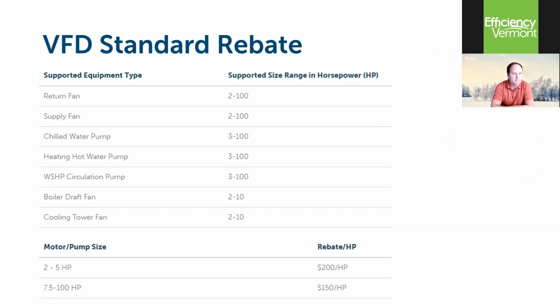Here it is in chart form. This is all off our website. I believe it's also on our VFD informational sheet, which I'll pull up at the end here. These are your 7 HVAC end-use applications. You'll see the cooling tower fans and boiler draft fans are tapped out at 10 horse. There aren't too many boiler draft fans over 10 horse in Vermont that I've seen, but maybe there's a few. These would just be handled custom. I don't know why we have the cap on that at 10. It doesn't mean we won't handle above 10.